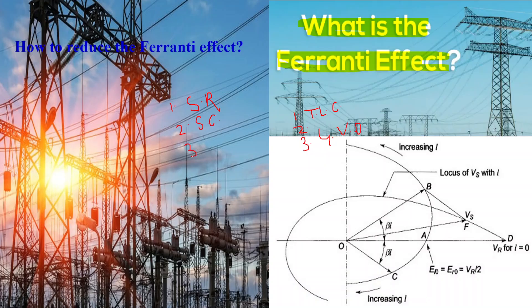Third, synchronous condensers. Synchronous condensers are rotating machines similar to synchronous motors but operate without a mechanical load. They provide reactive support to the transmission line, helping to stabilize voltage levels and mitigate the Ferranti effect by absorbing or supplying reactive power as needed.